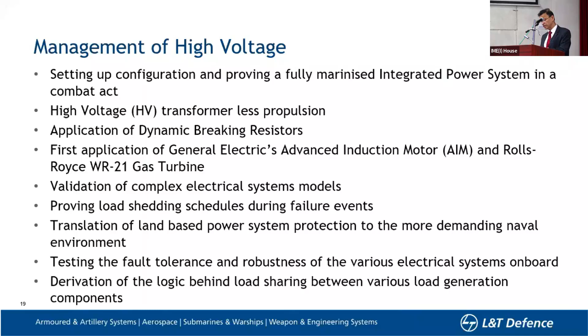All these technologies were being used for the first time, so they had to be tested in a shore-based facility to prove the concept: validation of complex electrical system models, proving load shedding and schedules during failure events, translation of land-based power system protection to the more demanding naval environment, testing fault tolerance and robustness of the various electrical systems on board, and derivation of the logic behind load sharing between various load generation components.